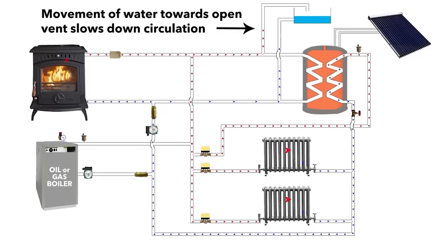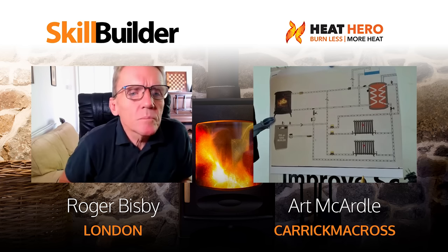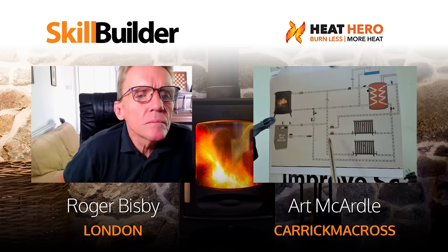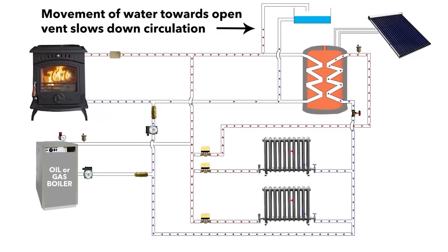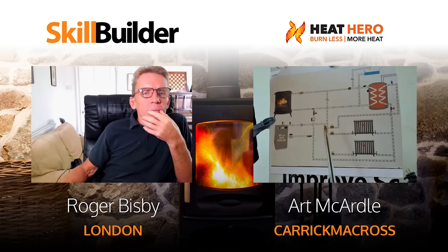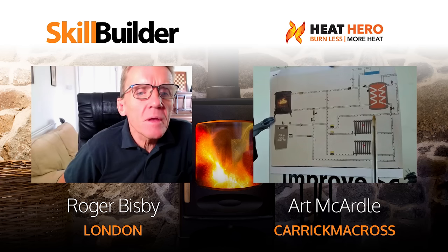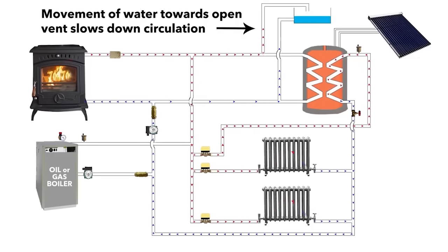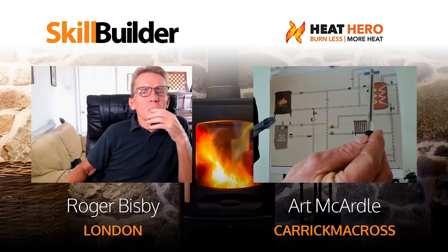The water passes slowly through the stove towards the radiators, which you see on those far-away radiators. As with plumbing, water takes the path of least resistance - if you allow water to go somewhere you don't want it, like up the open vent, that's where it'll go. When the system is idle it sits at about 0.5 bar of pressure. As soon as the pump comes on that 0.5 drops to zero. The neutral point is where the cold feed comes in just by the cylinder, but it doesn't fix the pressure problem.